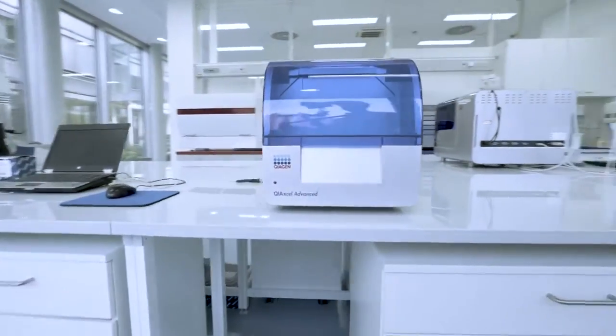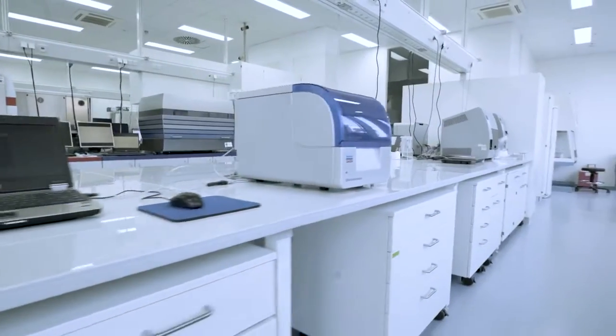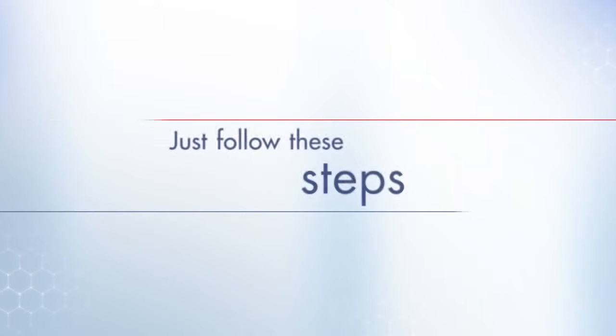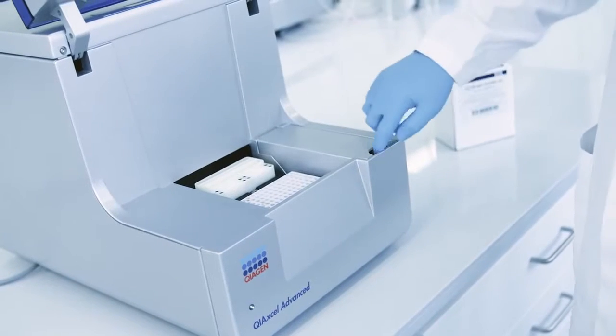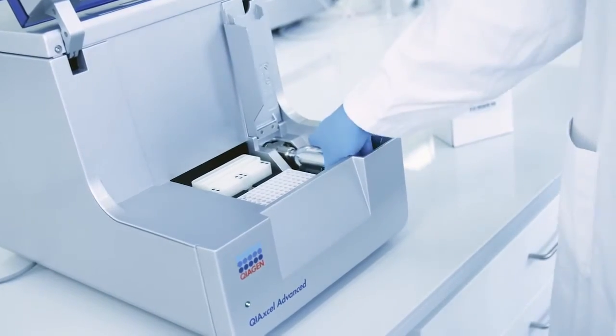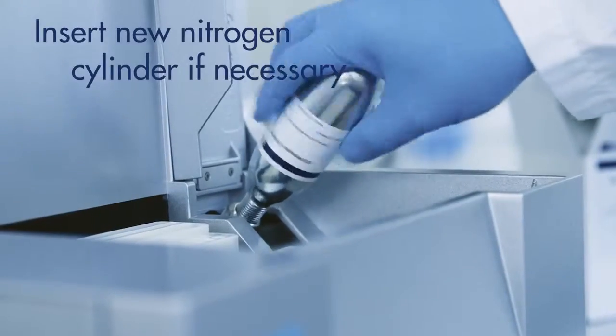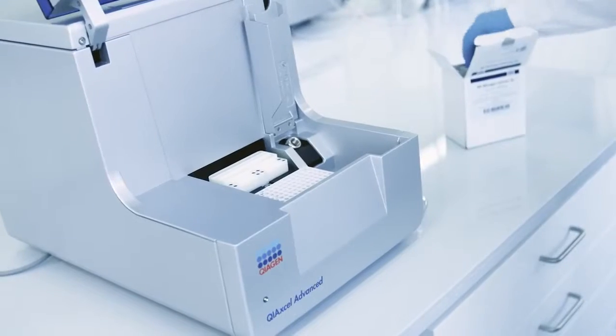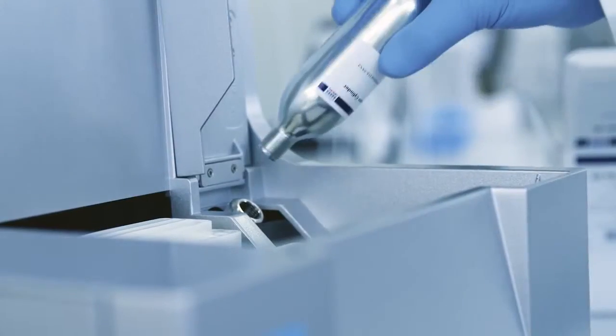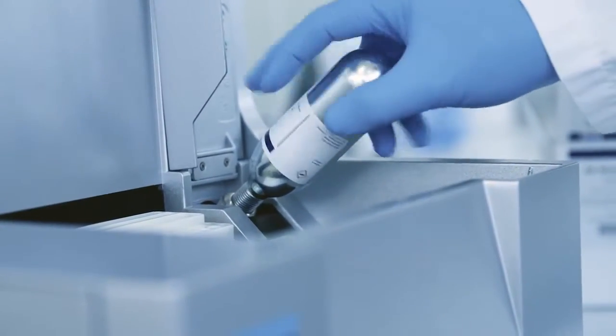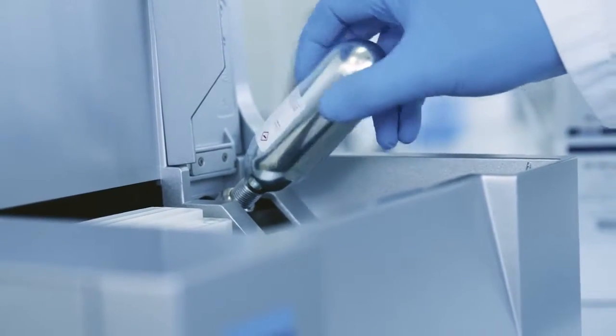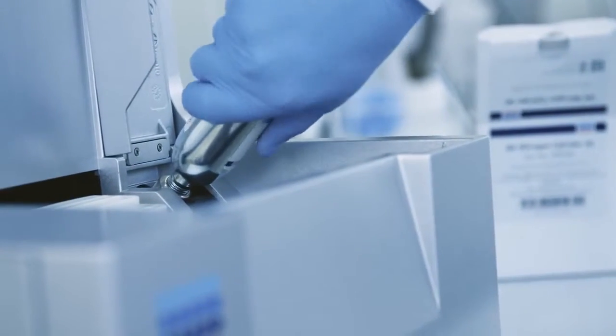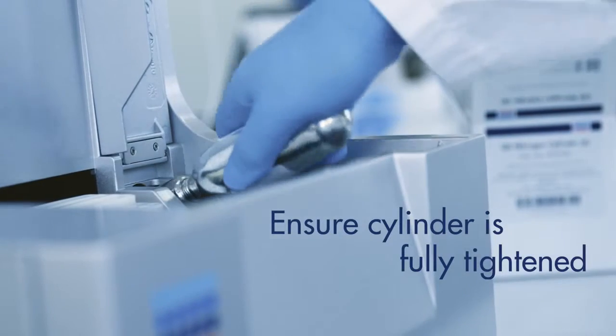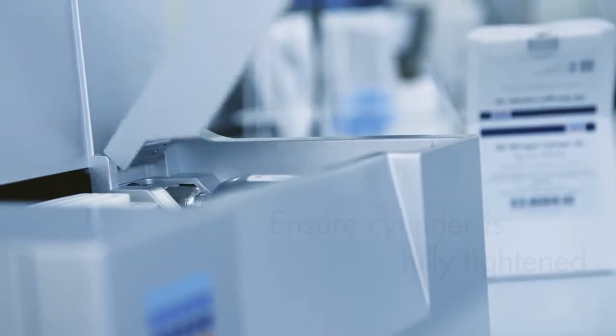Preparation of the QIAxcel Advanced prior to analyte analysis is easy. Just follow these steps. Make sure that sufficient nitrogen is available. If necessary, insert a new nitrogen cylinder into the QIAxcel Advanced. It is important to ensure the bottle is tightly inserted to prevent nitrogen leaks. After the cylinder is pierced by the instrument, make sure that it is fully tightened.